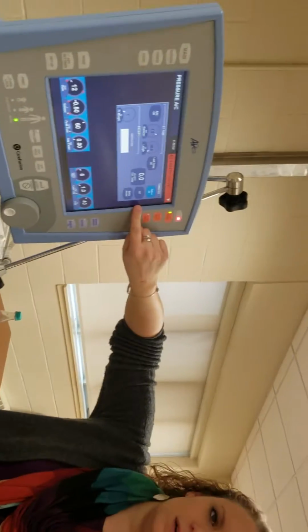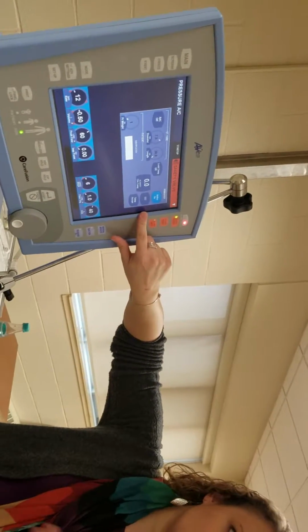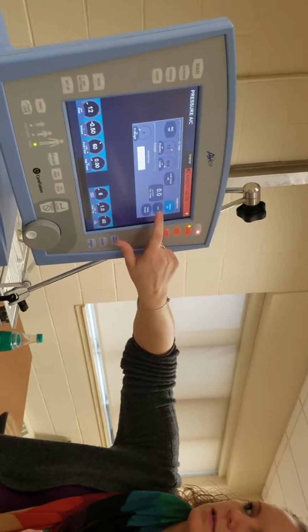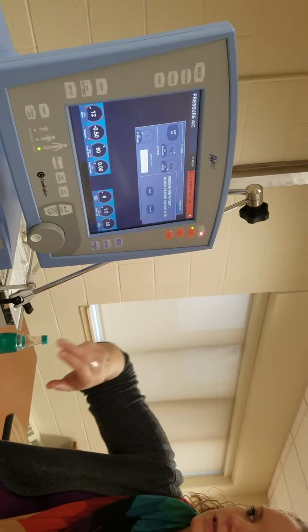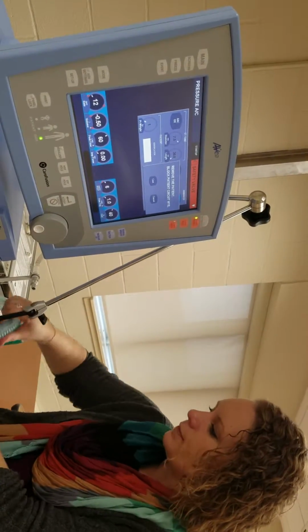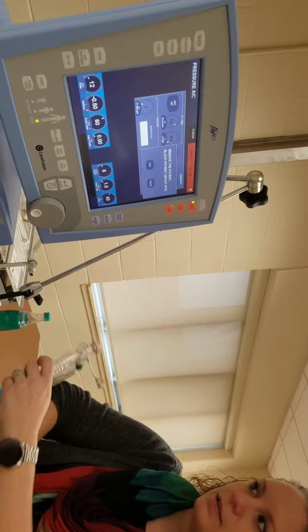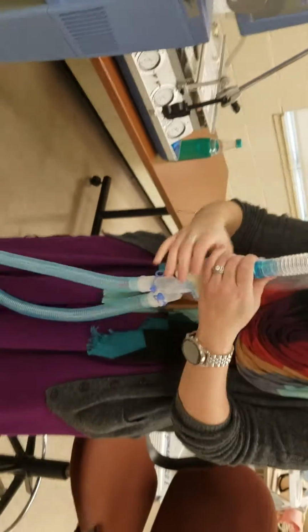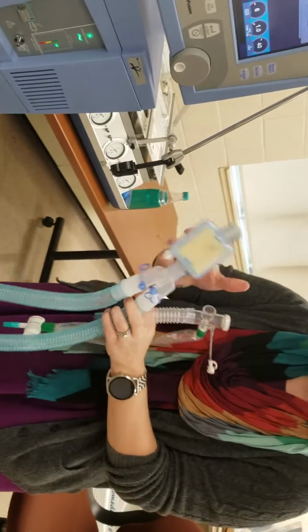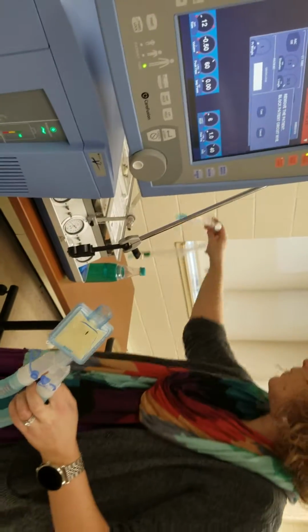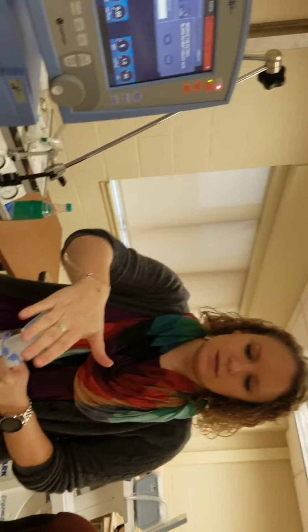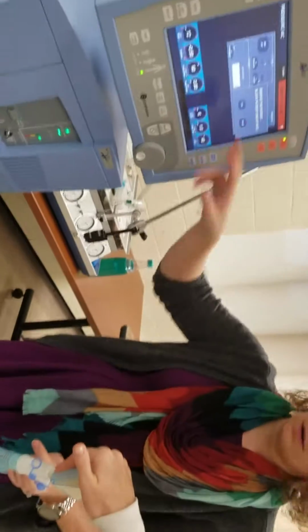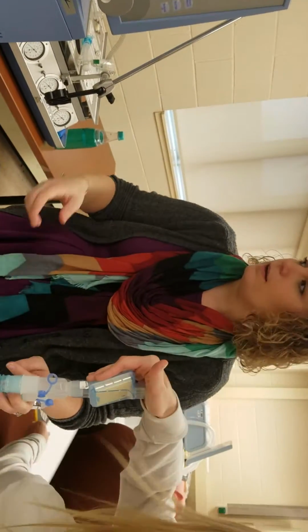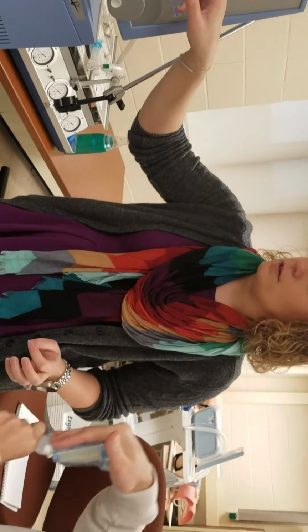Your EST, or extended system test, is how we do our leak test. So you're going to hit that button first, EST, and it gives you some instructions. We want to make sure that we're not hooked up to a patient because it's not ventilating right now. And then what we do is we need to block the Y. So if one of you would like to take and block the Y, make sure you hold pressure on that. And then the next thing we're going to do, if it's easier, you can take it. And we'll go ahead and hit continue.